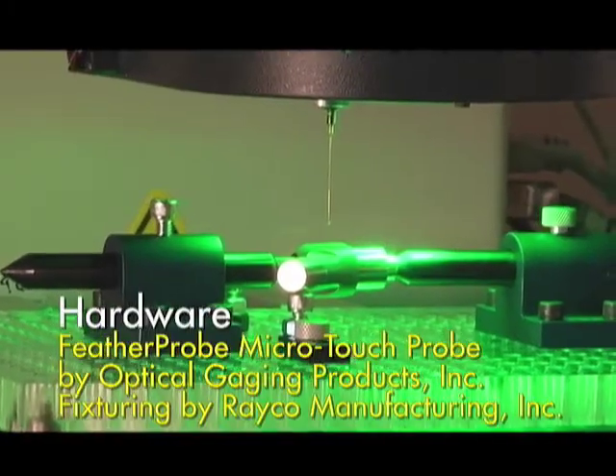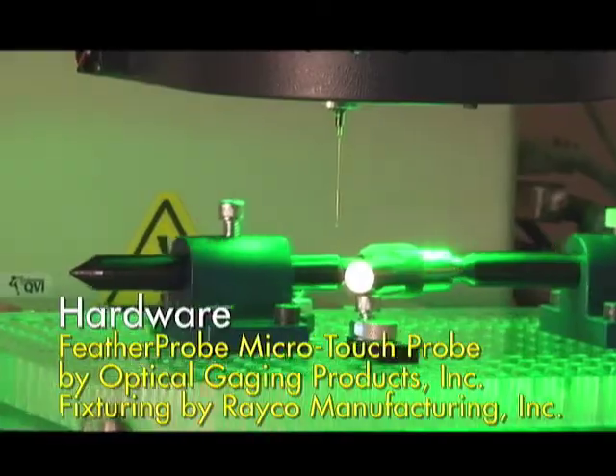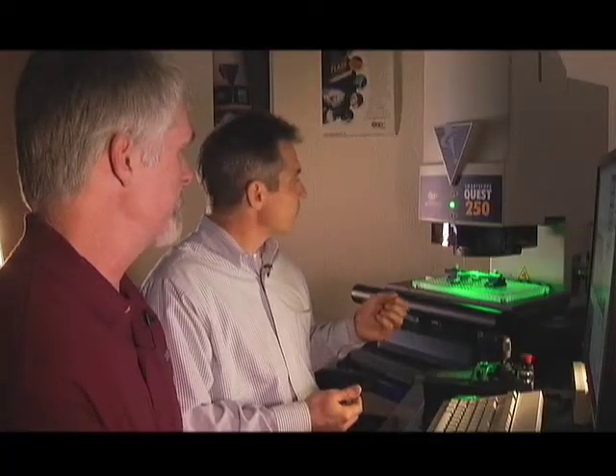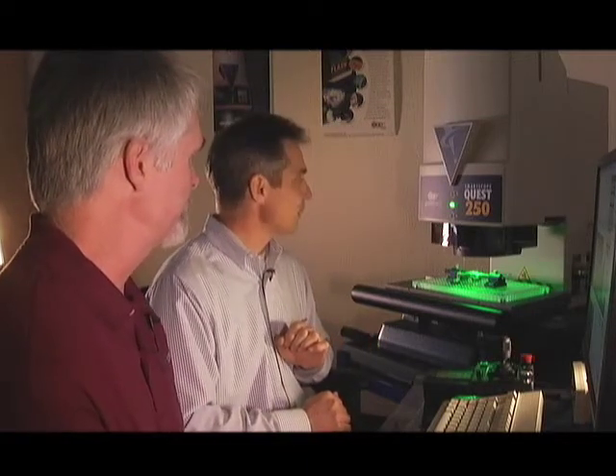In this case, we have another type of microsensor. It's a contact microsensor. You're probably familiar with the traditional Renishaw style touch probes that go on a coordinate measuring machine. Well, it's like that in that it has a ruby stylus hanging off of a stem here, and we're going to go around and make contact with the part to acquire data, but the technology behind it is quite different. This particular one is called a feather probe, reason being that it has an extremely light touch. Okay, how light? Down to 1 milligram of gauging force.